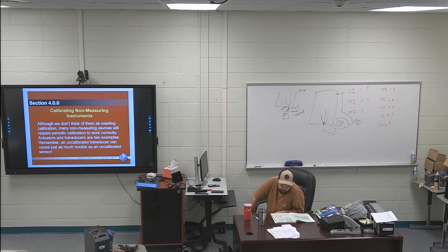Right hand side of page 25, the second paragraph, the whole thing is highlighted. Figure 17 shows the internal components of an I to P transducer. It is an electropneumatic device that accepts a 4 to 20 milliamp signal and converts it to a pneumatic signal. This conversion is accomplished by applying a current to the coil that creates a magnetic field. That's the biggest part to key in on. You're applying current to a coil that creates a magnetic field, which causes a flexible arm to move.